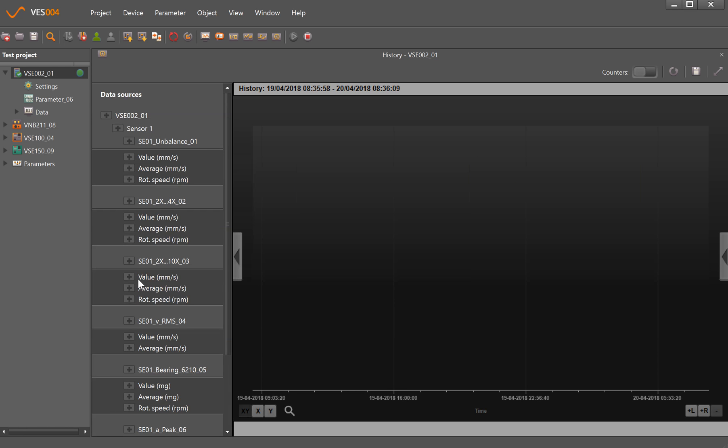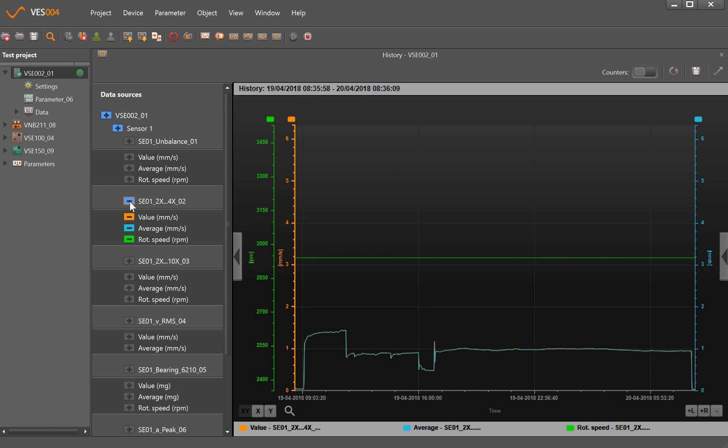So if I bring this tab open again, we'll pick two or three parameters just to have a look at and see what information was gathered. So if we look at sensor one 2x to 4x, this is monitoring primarily for misalignment issues. If I just click beside it there, that's given me three graphs here: the orange one is the maximum value in millimeters per second, the blue is the average value, and the green is the rotational speed. You can see it's a fixed speed machine, so the green line here across is just showing that the speed didn't change throughout the whole period of this history trend.